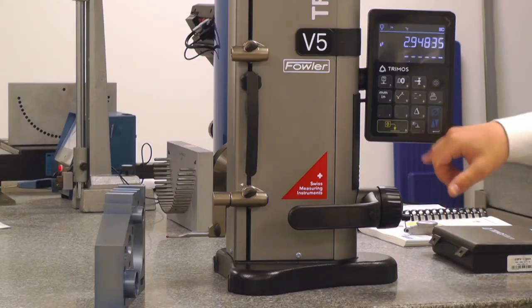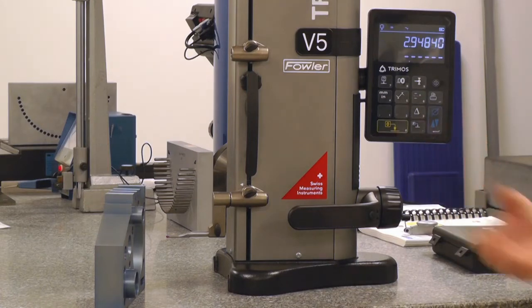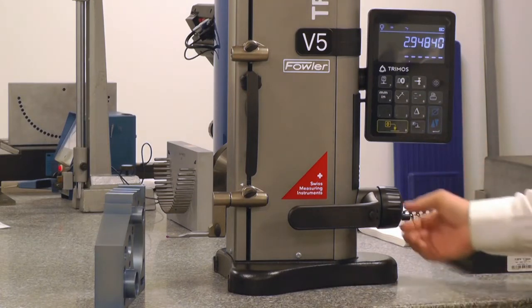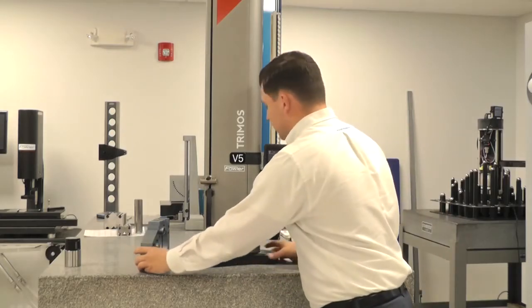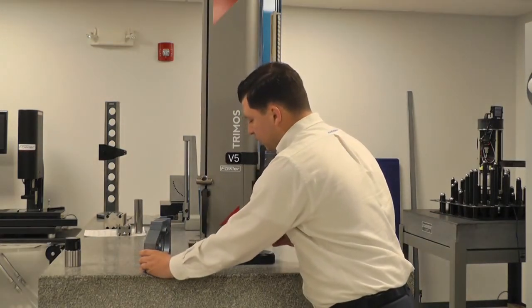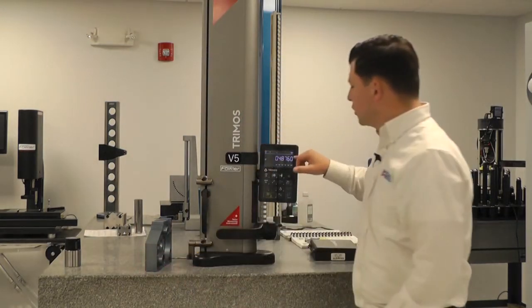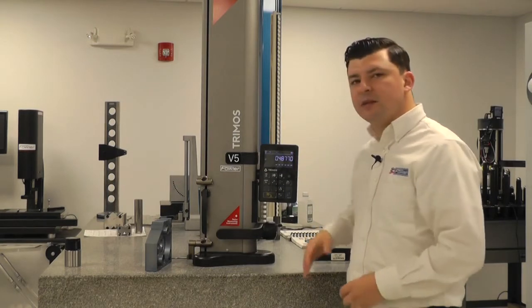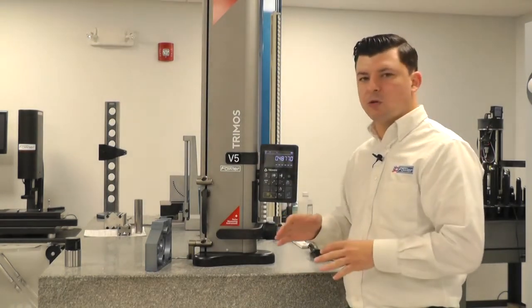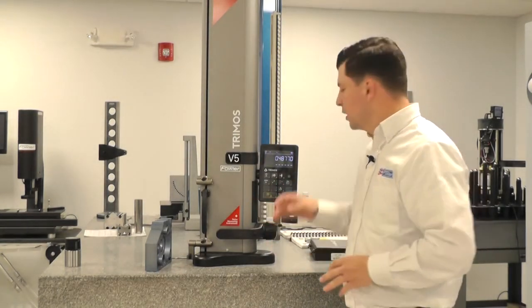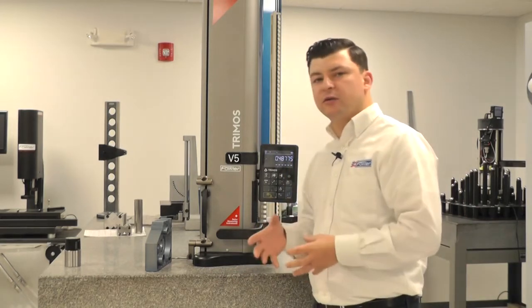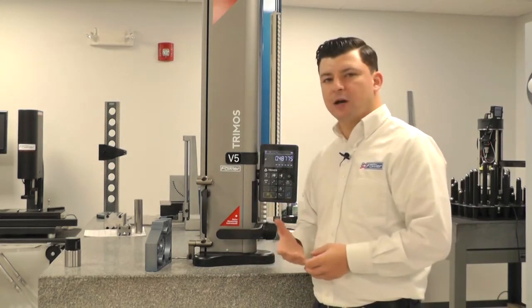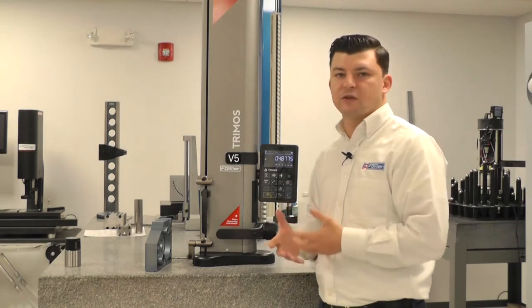So if I trigger the number 5 key, I'm looking at the minimum value. That's going to find the lowest point. If I come in here and engage my probe, you're going to notice that the top line is always going to be a live indicator of wherever the probe is, high or low, it doesn't matter. The bottom line is going to follow those values until we sweep through the bottom, and it's going to lock on the reversal point for us.